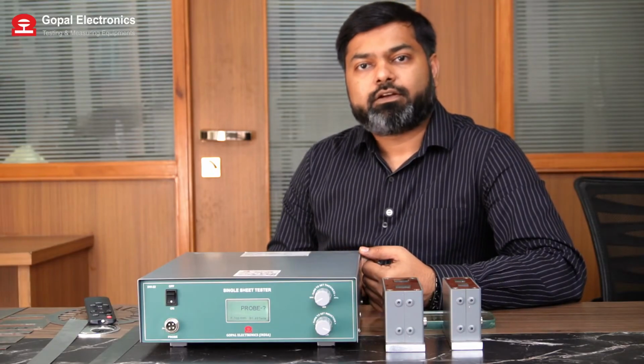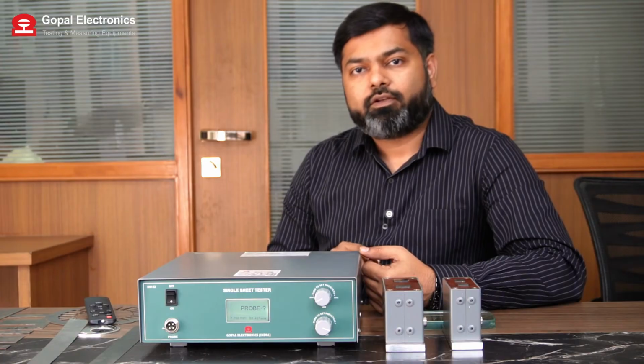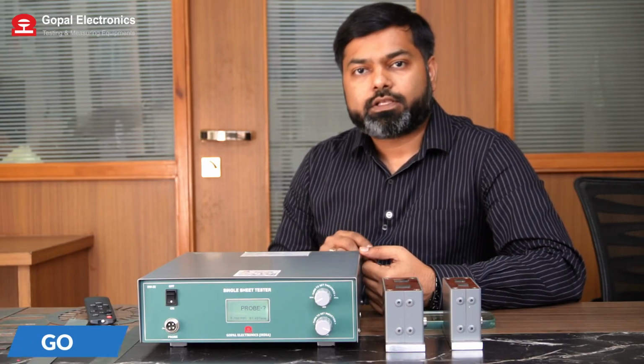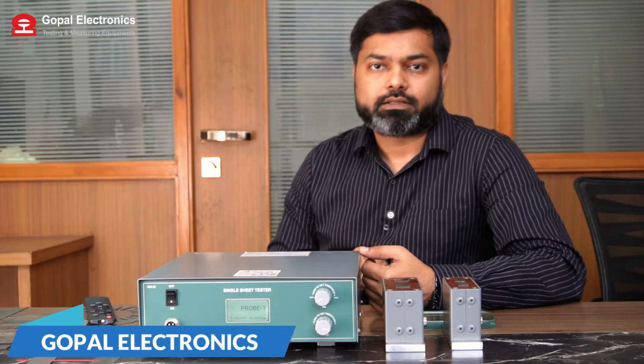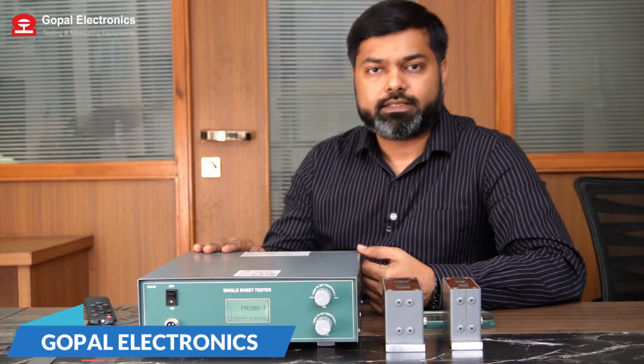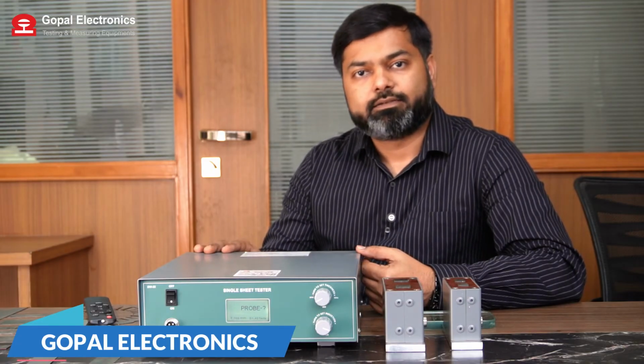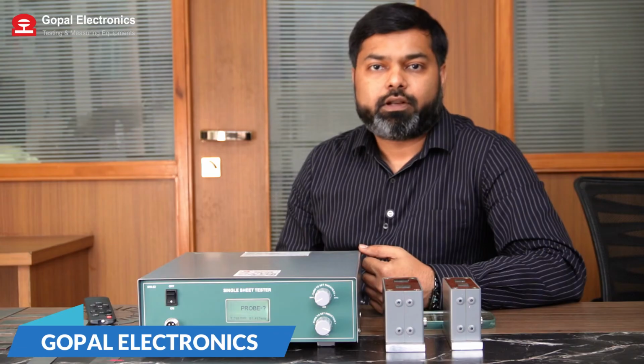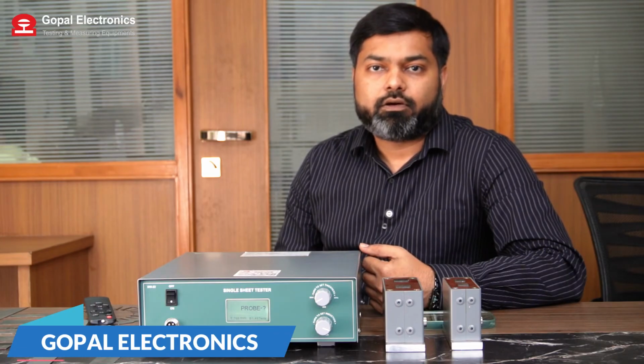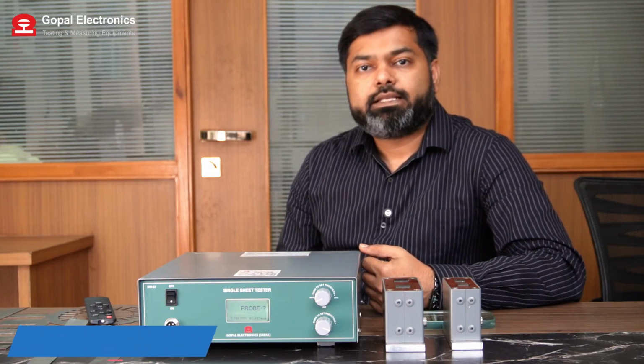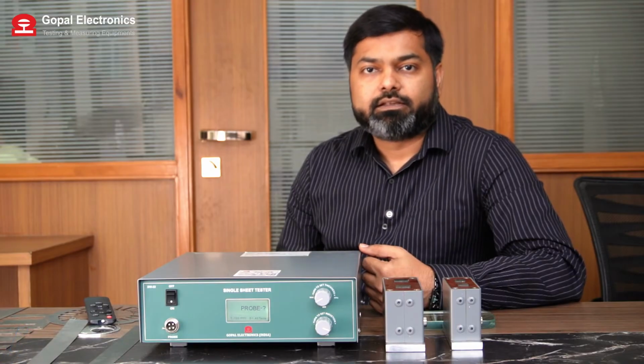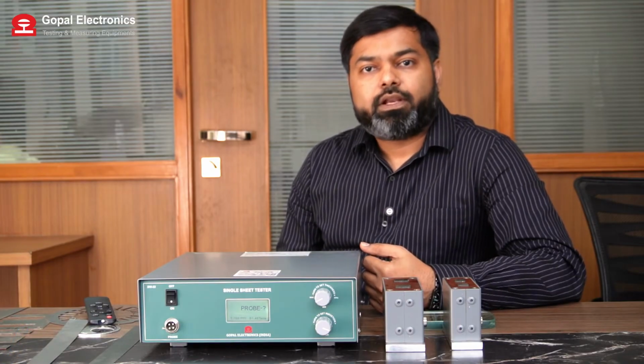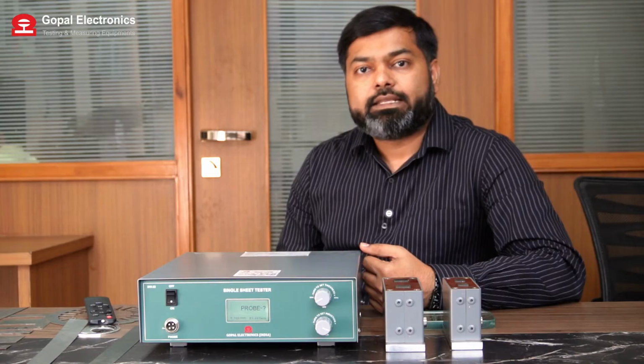If you are a manufacturer of transformer, motor, fan or pumps, and if you are focused on designing high efficiency products, then investing in a single sheet tester would be a wise decision. When designing energy efficient products like fan, motor or transformer, minimizing the core loss is very essential. And that's why manufacturers require the right testing equipment.